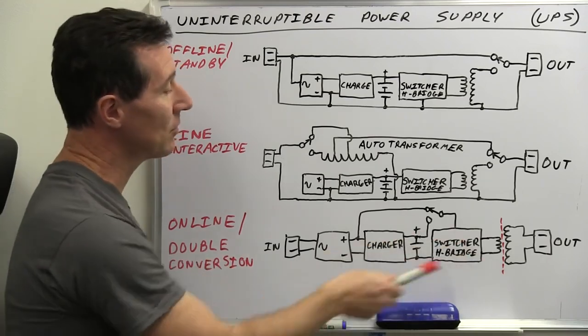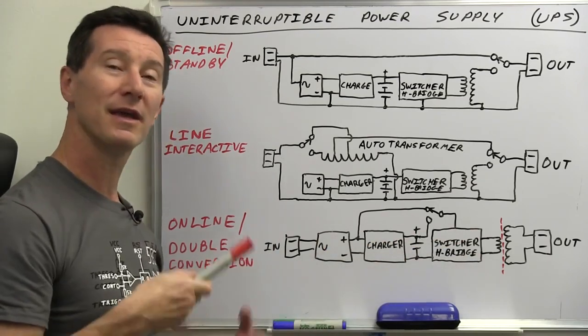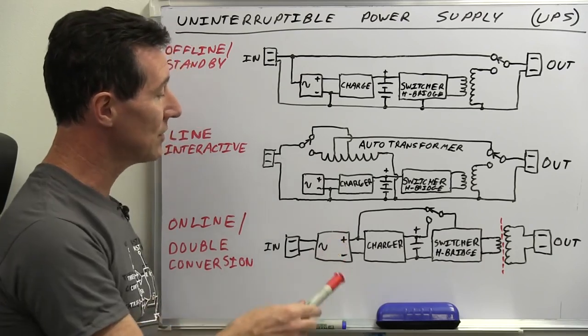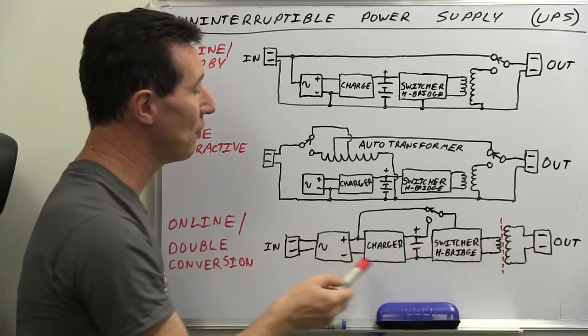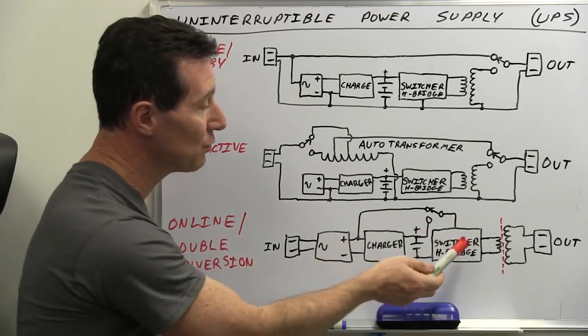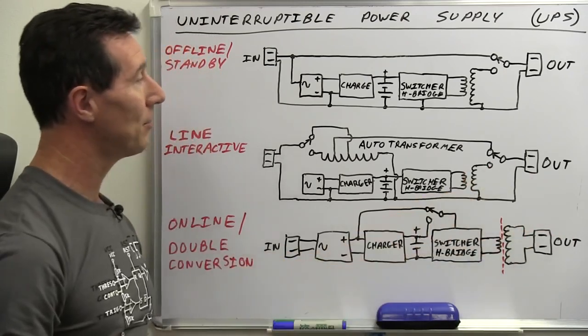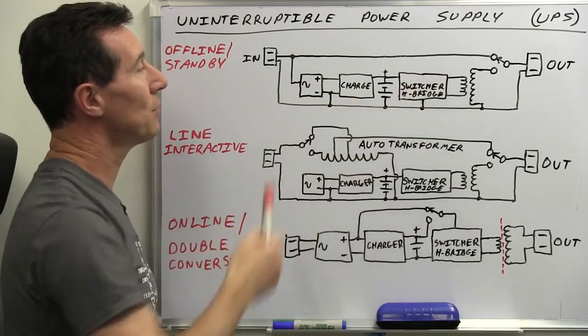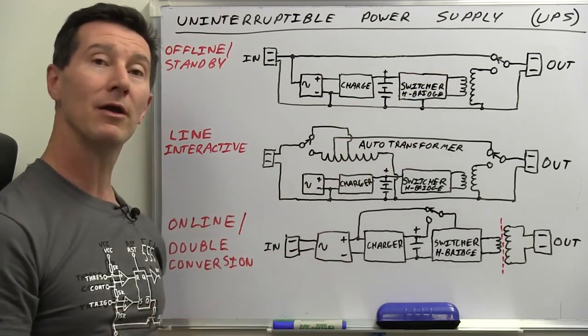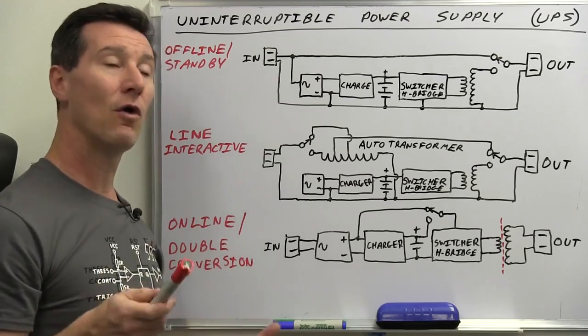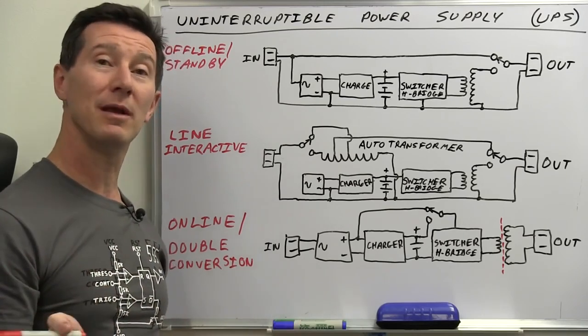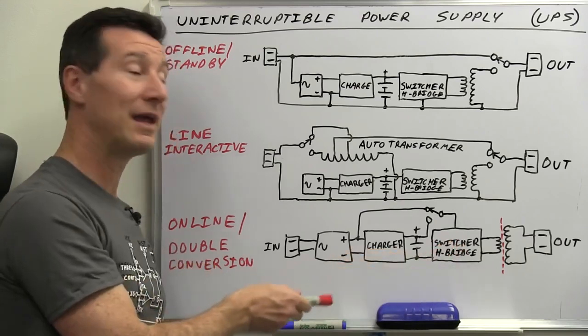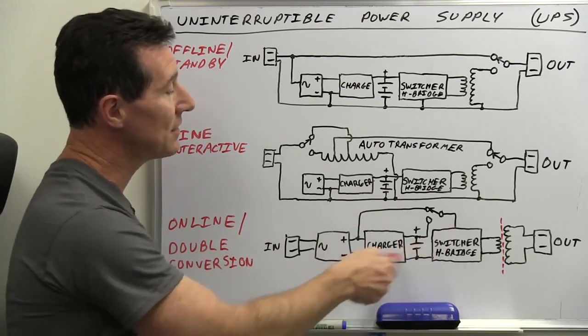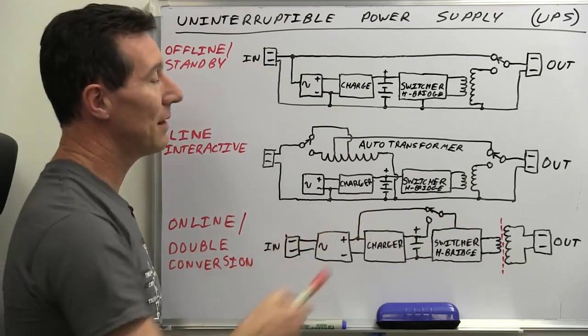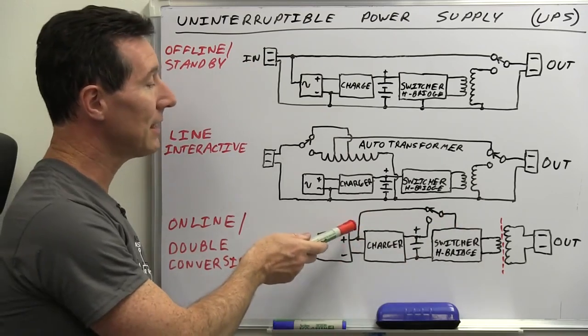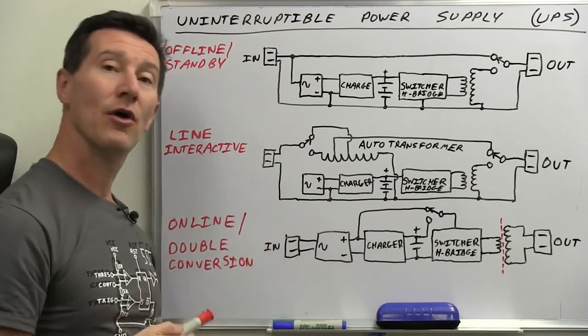So that's why these things are more expensive and more difficult to design. They're going to run hotter, things like that, because the circuitry inside has got to deliver that full load, and then you've got losses in there, and the switcher has always got to be operating and delivering the output load. Whereas up here, your switcher or output load might only need to be sized and designed for operation for 10 minutes, 30 minutes, for example. But this thing has got to work all day, every day, 24/7. So this thing needs a lot more cooling and a much better design. So that's why it's typically more expensive to design an online UPS.